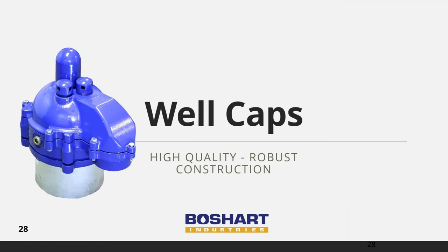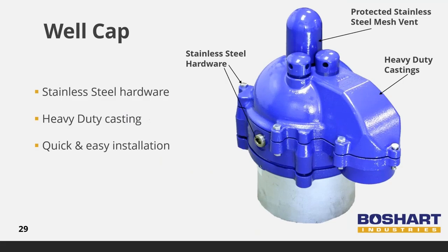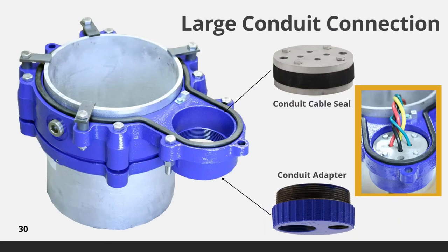We will now take a look at well caps. The well caps are constructed from heavy duty cast iron with powder coat finish for corrosion resistance. The sealing gaskets are robust, molded from Buna N rubber for excellent sealing. All nuts, bolts, locking pins, and 24-mesh vent screen are stainless steel. Boshart well caps are designed with a 4-inch FPT conduit connection, which provides ample room to install the heaviest pump cable with ease. Optional cable seals provide a watertight, vermin-proof sanitary barrier between the conduit and the well chamber.